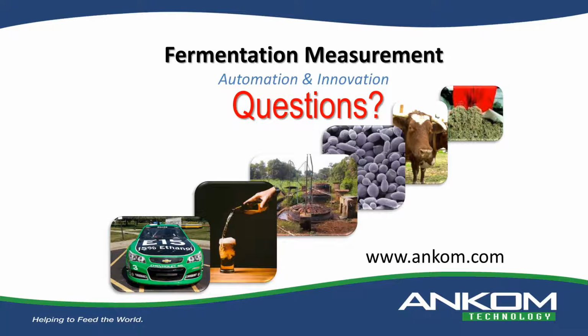One thing to add to that is, as Joe said, it's not meant to be a measure of the temperature of your water, things like that, because we don't submerge it. We do offer extensions for the temperature sensor in order for you to have the measurement outside of the module itself. But the key is that over time it'll equilibrate to your environment if it's a closed environment. One of the reasons why we went with the temperature sensor was to be able to monitor, if you will, at a glance, if there was anything happening in the incubation system that was being used. In other words, was there a sudden drop in temperatures and things like that? Because changes in the temperatures would affect your gas production, and we want to be able to see. It's kind of a troubleshooting thing, if you will, more than anything else. But as Greg suggested in his presentation, there's been some neat applications for that temperature sensor.